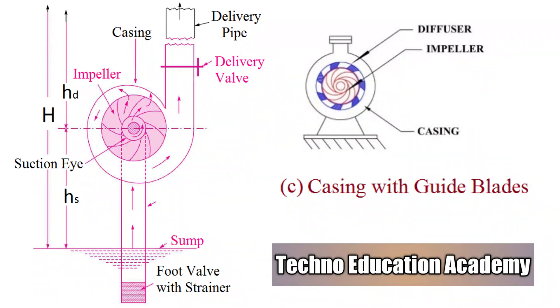Third one type of casing is casing with guide vanes or diffuser type. Here an impeller is surrounded by series of guide blades mounted on a ring which is known as diffuser. The guide blades are designed in such a way that the water from the impeller enters the guide vanes without shock. Also the area of the guide vanes is increased thus reducing the velocity of flow through guide vanes and consequently increases the pressure of water. This pump gives more pressure head as compared to vortex types and volute types construction. The diffuser type of pump has therefore higher efficiency. These pumps are also called turbine pumps.